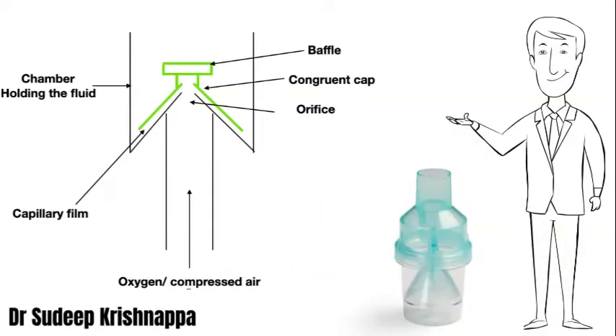Oxygen is fed from the tubing at the bottom; the pressure drop happens at the orifice, generating subatmospheric pressure. Instead of a capillary tube, we have a cap highlighted in green. The shape of it is congruent to the base and the orifice — it sits on top, providing a very small gap between the two which acts like a capillary tube. The fluid in the chamber is continuously suctioned up through this small gap towards the orifice, where the jet shatters the liquid against the baffle internally to generate the aerosol and mist, which subsequently moves on towards the patient.